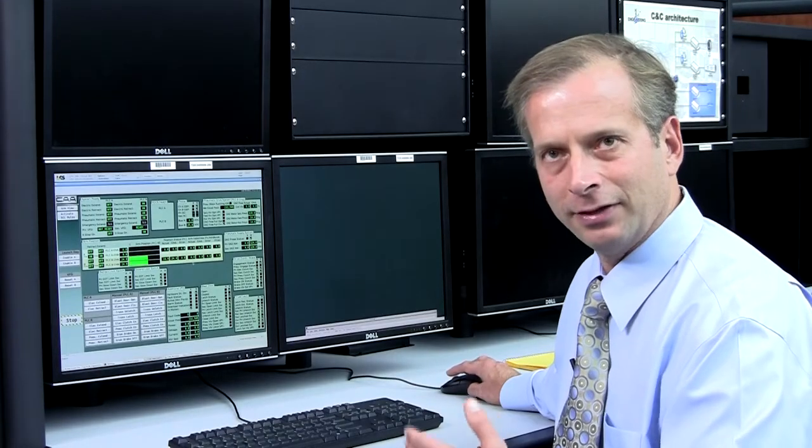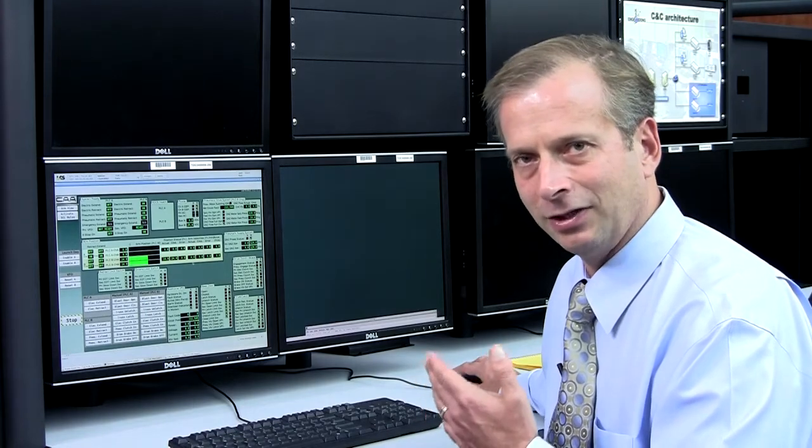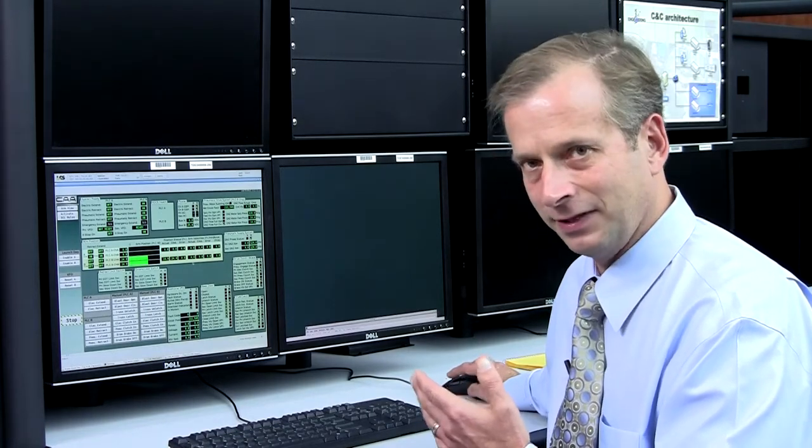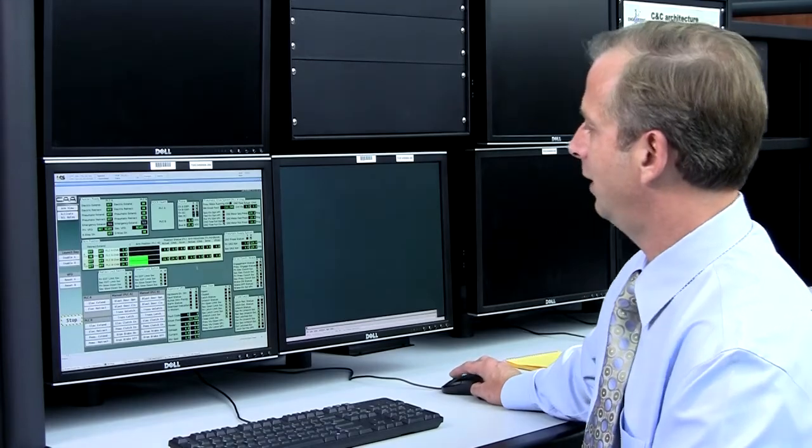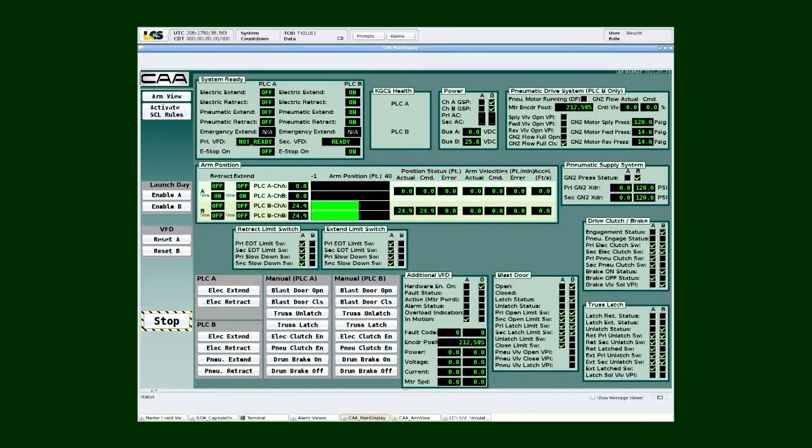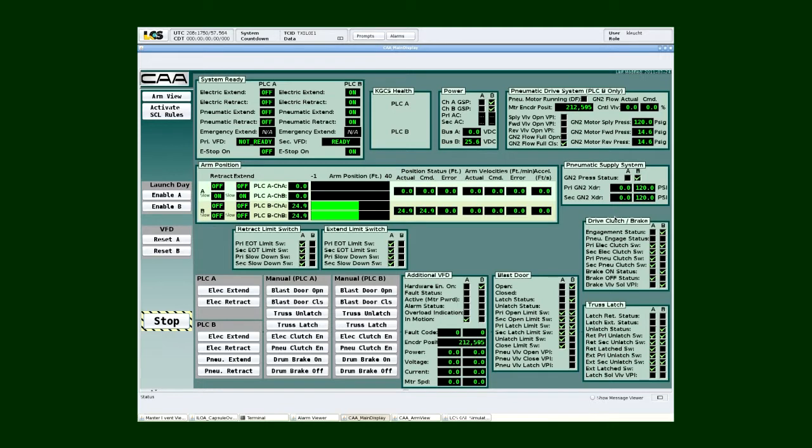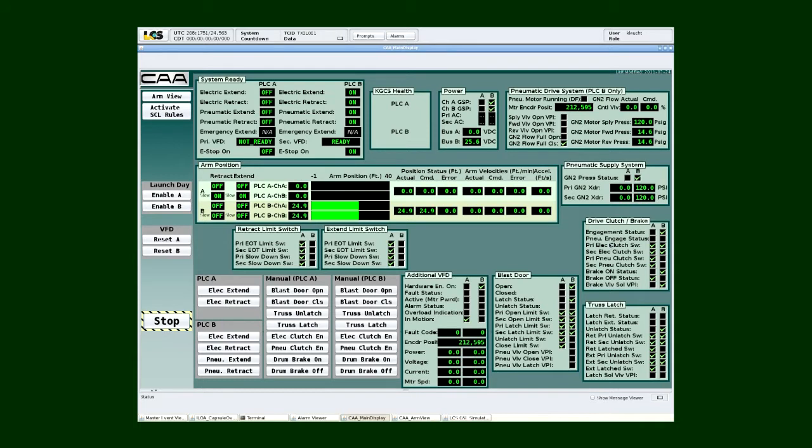The next thing that we're going to demonstrate is the ability to actually control this system from the pneumatic system. And if we take a look at the screen currently, the pneumatic drive information is in the upper right-hand corner of the screen. And it tells us our current supply pressure to the system is 120 pounds per square inch. Our current forward and reverse pressure to our motor, because it's off, is atmospheric pressure, which is indicating 14.6 or so pounds per square inch. And if you also notice, we have the drive clutch brake mechanism. Now the function of the drive clutch brake mechanism is that it provides the ability to disconnect the electric drive and engage the pneumatic drive if we're on the pneumatic drive and vice versa if we're on the electric drive. And of course that is because in the event we have a damaged pneumatic motor, we want to be able to decouple it automatically from the drive system in case it is damaged and couple it only to the active system. The drive brake mechanism is responsible for holding the arm in position when we're not in the fully extended or the fully retracted positions.